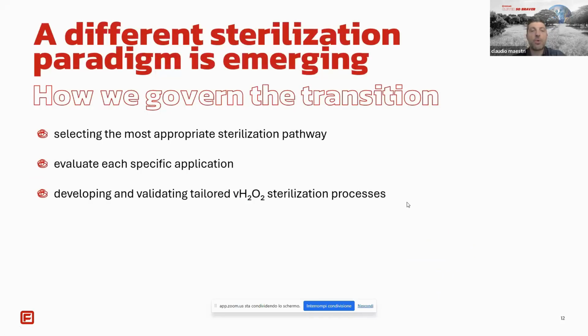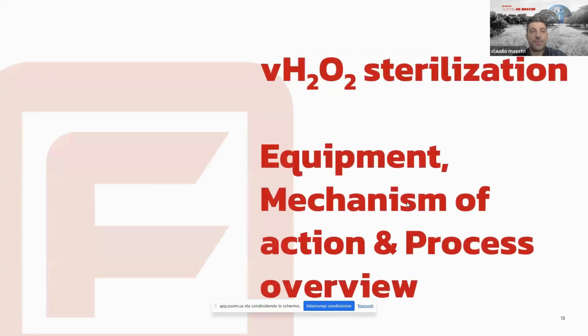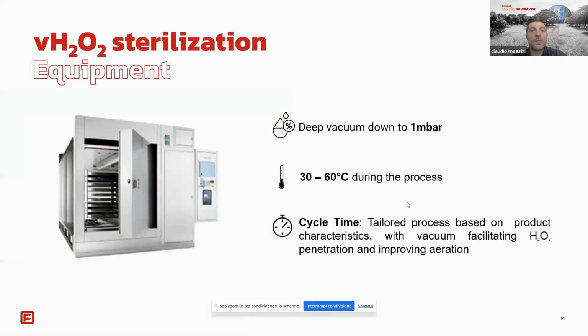As Fedegari, we are able to guide you in selecting the most appropriate sterilization pathway based on material compatibility, working alongside you in our tech centers to experimentally evaluate each specific application, developing and validating tailored H2O2 sterilization processes for highly complex devices, ensuring safe and reliable outcomes. So here we see the main features of this process: a pressure down to 1 millibar if necessary, a temperature from 30 to 60 degrees, a tailored process based on product features, with vacuum facilitating H2O2 penetration and improving aeration.